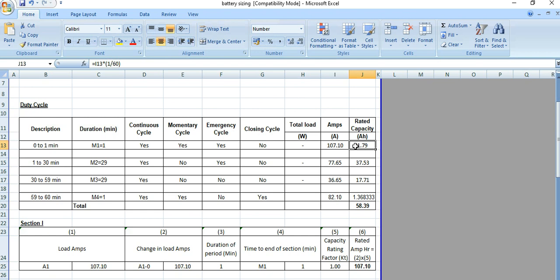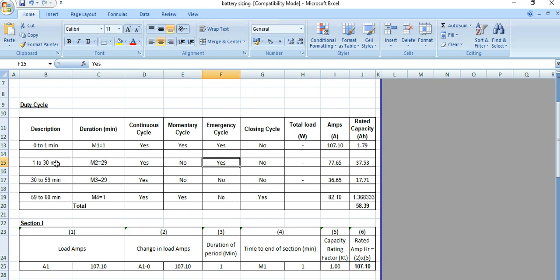The rated capacity equals I13 multiplied by 1/60, because this is the 0-to-1 minute load — it will be multiplied by 1/60. Next is the 1-to-30 minute load. That is basically a 29-minute operation. Here we have continuous load; there is no continuous load change, so this is coming 77.65 ampere from the load calculation. This will be multiplied by 29/60 because it is a 29-minute duration load.